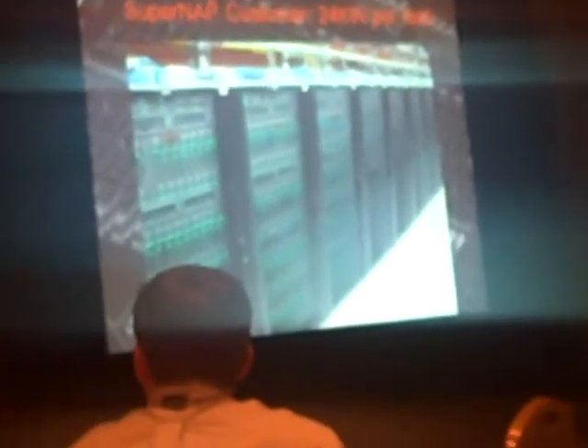...elementary school age kids. So if you stand next to their racks at about noon Vegas time, which is about 3 o'clock back east, the servers start firing up, because why? All the kids are getting out of school. They stay running hot until about 9 o'clock LA time, when kids that age are primarily going to bed. So they might be at 17 kW in the middle of the afternoon and go down to 1 in the middle of the night.